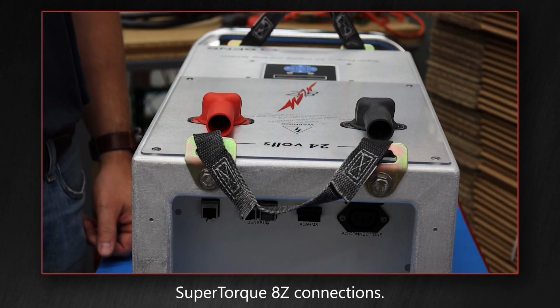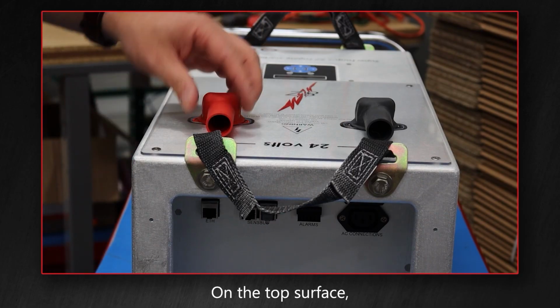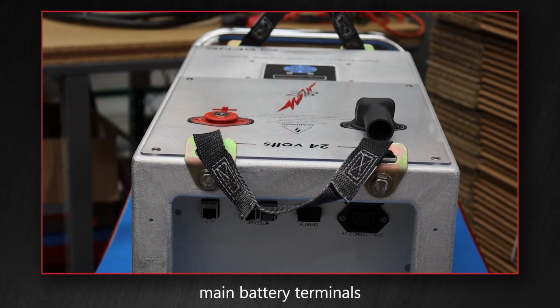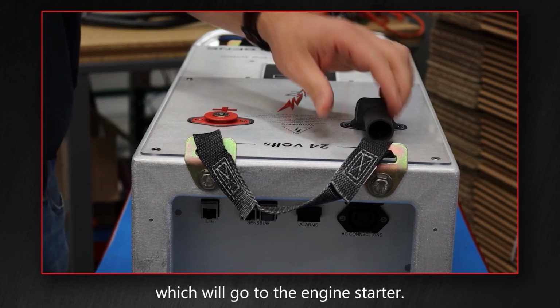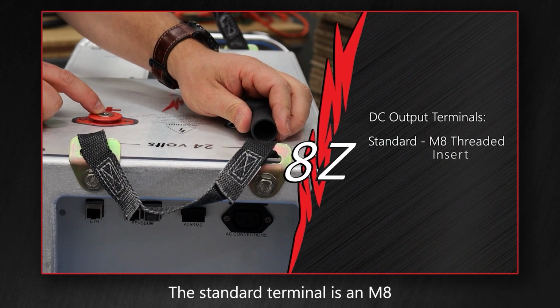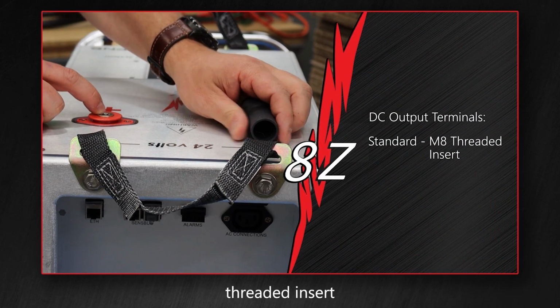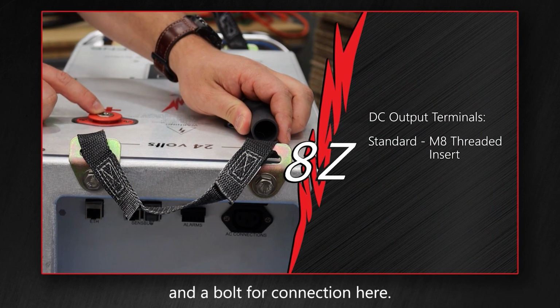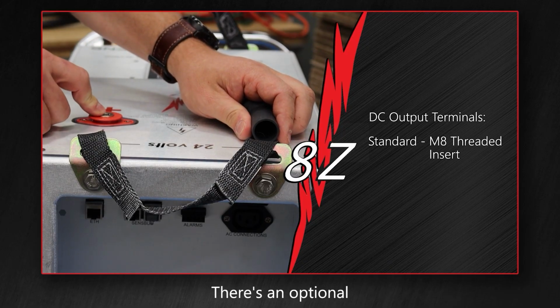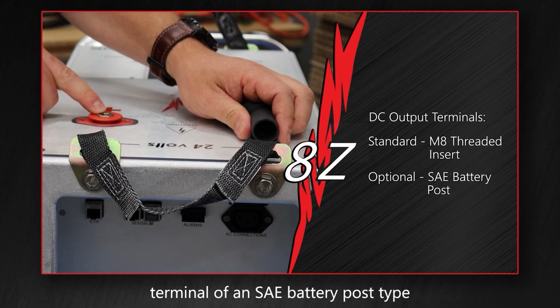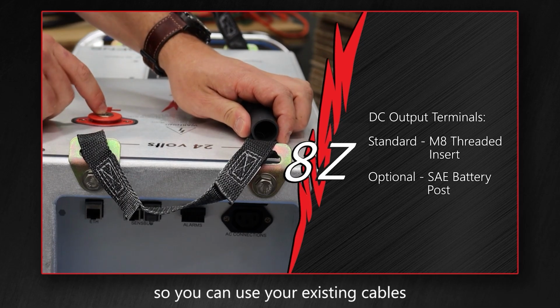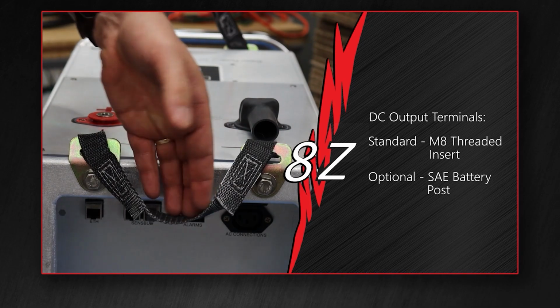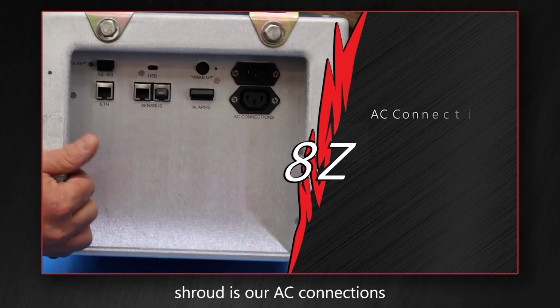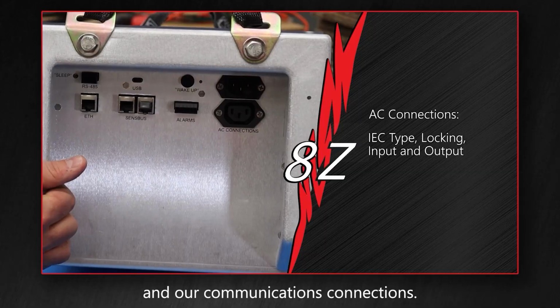So looking at our SuperTorque 8Z connections, on the top surface we have our main battery terminals, which will go to the engine starter. The standard terminal is an M8 threaded insert, so you can attach a ring lug and a bolt for connection here. There's an optional terminal of an SAE battery post type, so you can use your existing cables in the field. Here under this shroud is our AC connections and our communications connections.